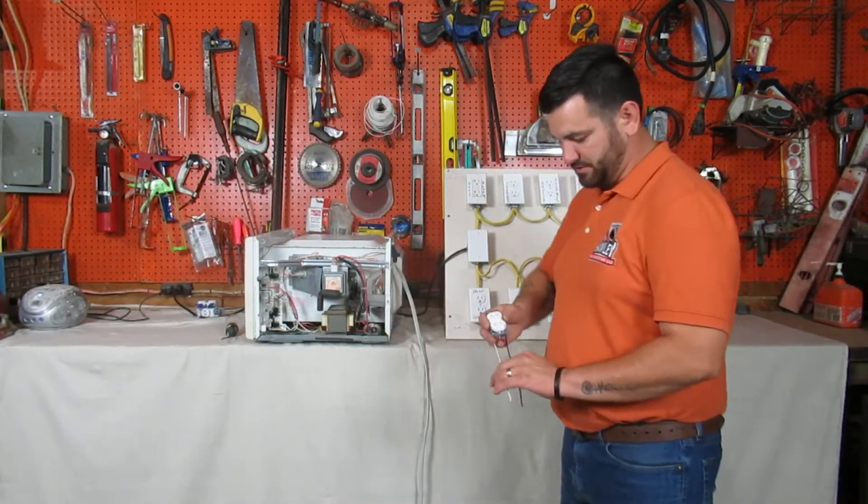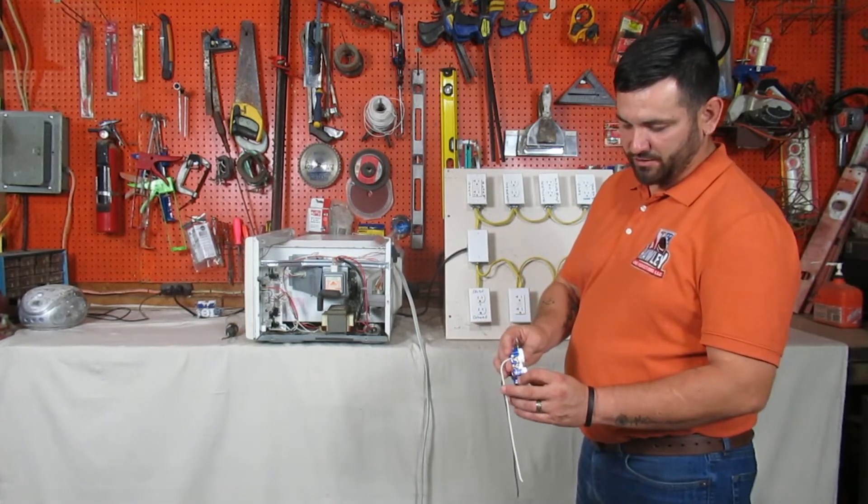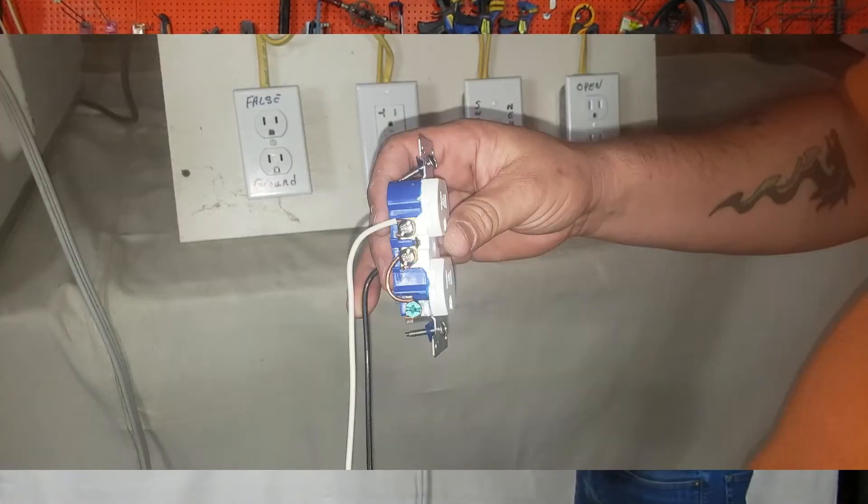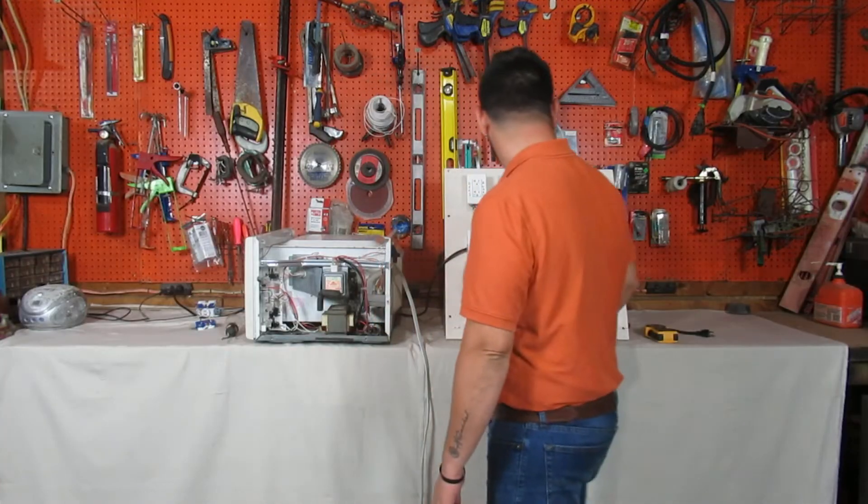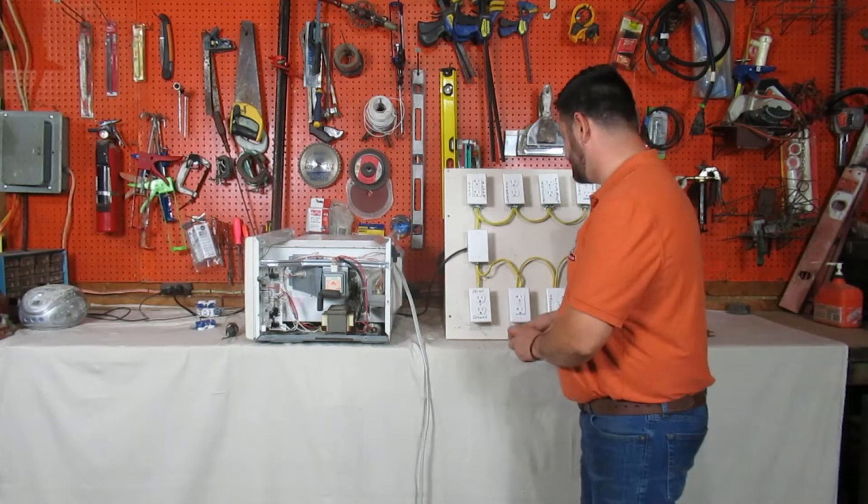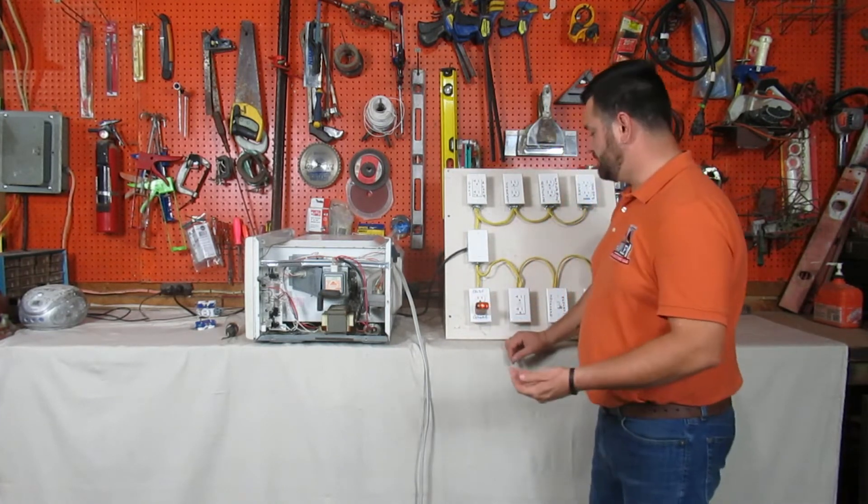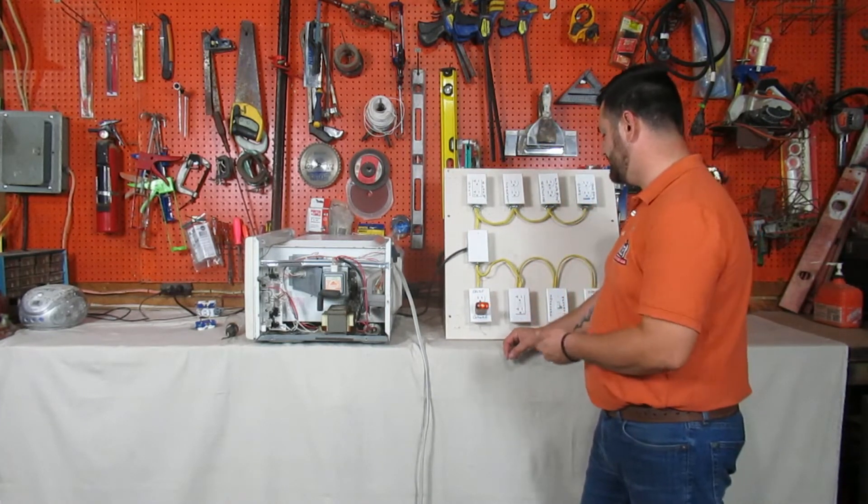So your outlet will appear to be grounded even though it's actually not. You will have no way of knowing this if you use a three-light tester here because it shows that it's grounded.